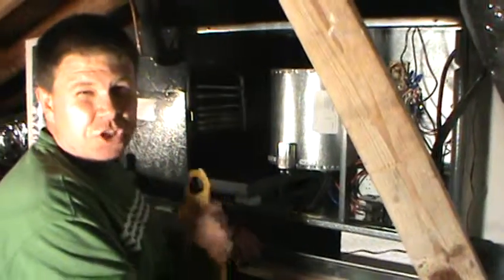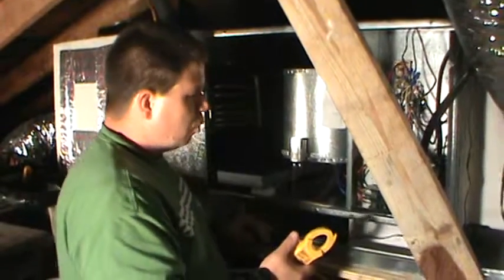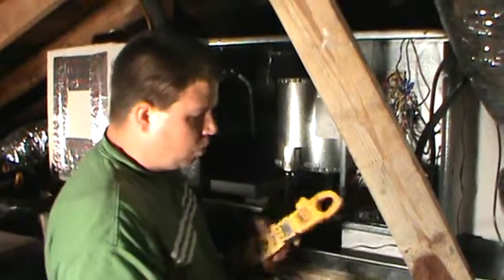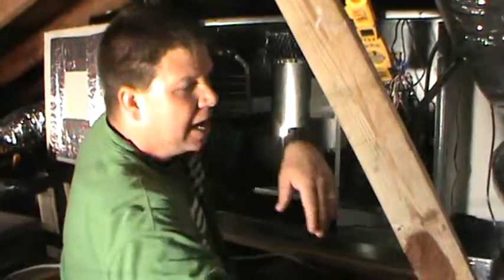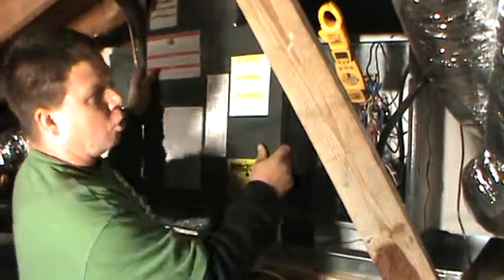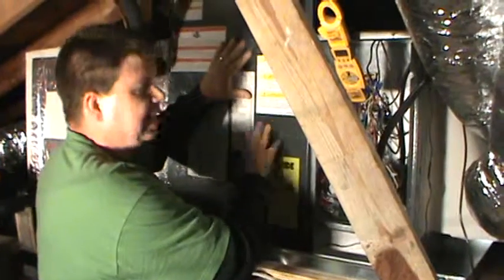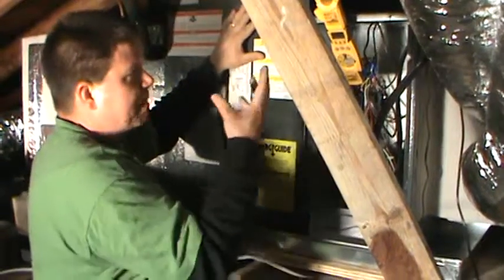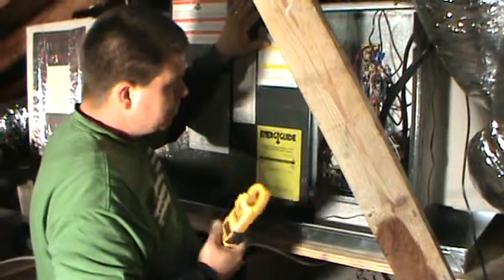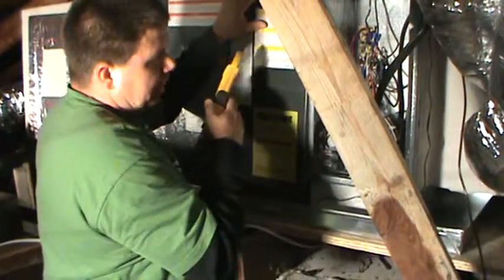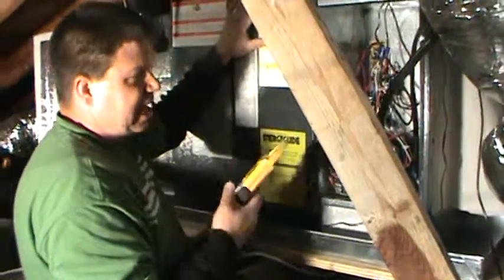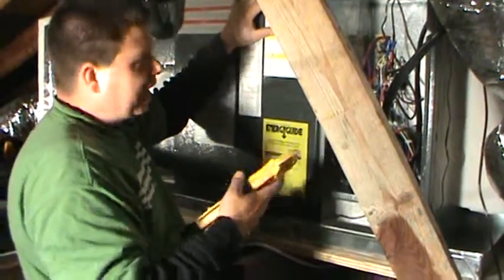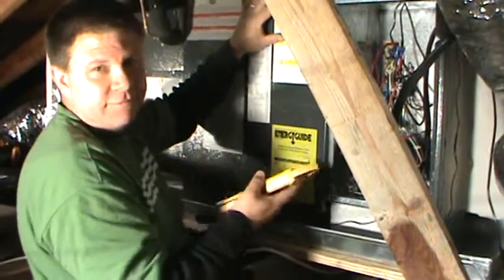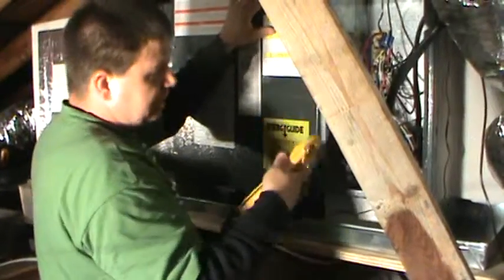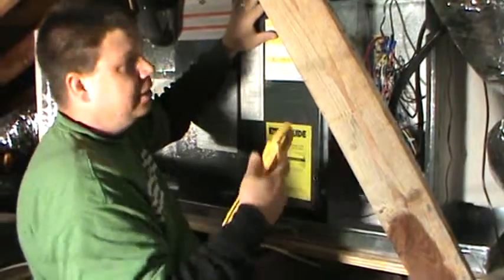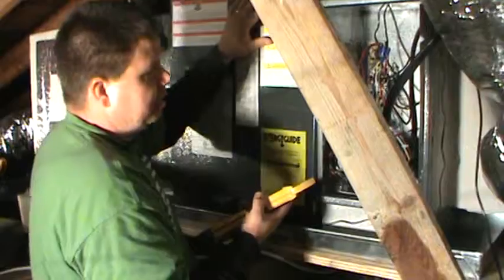This is not a variable speed, this is a 3-speed motor, so it's not as important to do this, but on a variable speed or an ECM motor, you will need to put the panel back in front of the blower part in order to simulate that the unit's closed, because then the motor will ramp up and you'll get the full amp reading. On an ECM and on the variable speeds, they have DC wires, so you're not going to check like this one you would on the 3-wire. It'll have 10, 15 wires, so you're going to want to check using the high voltage wires coming into the unit. That'll give you the full load of the motor. It's the only device pulling amps.